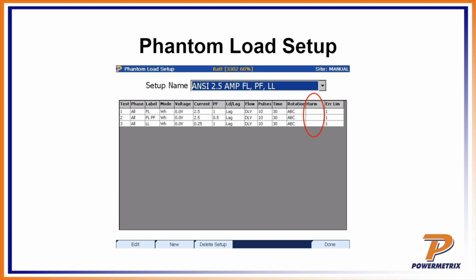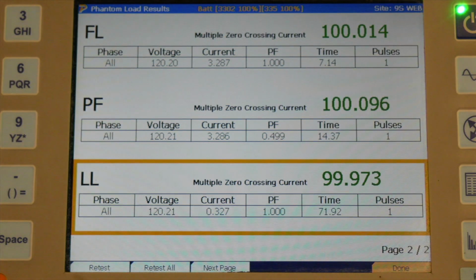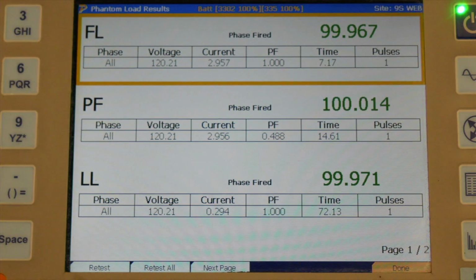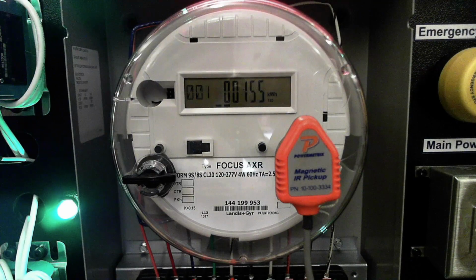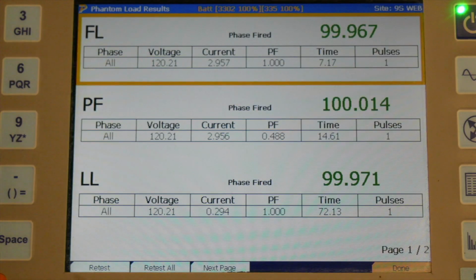And then, Jared, if we go to the 3 series now, the tests that I've run are complete. What I did is I first did a phase-fired waveform, and the meter performed very, very well. I'm actually running a test on a Landis+Gyr Focus AXR, so very, very good. And all the ones that we've seen so far as solid-state meters go, they seem to perform well on these crazy waveforms with high harmonics. What we have seen is that mechanical meters do not do as well.